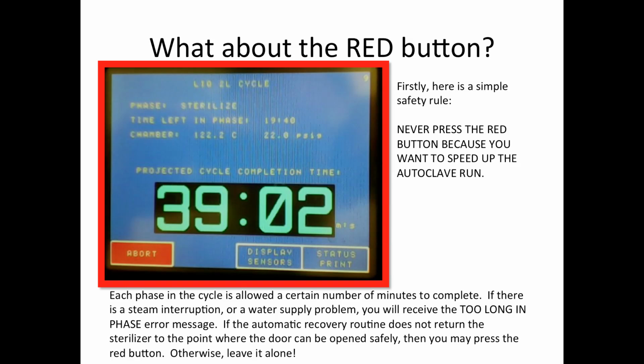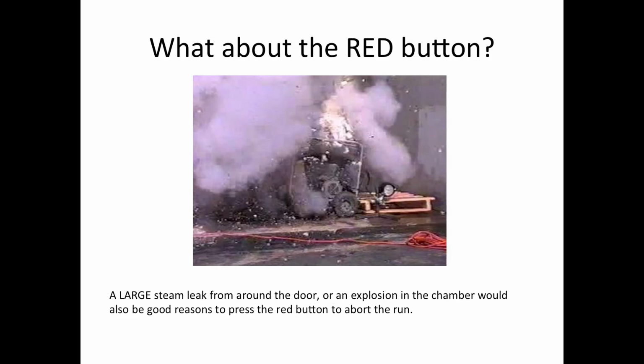Otherwise, leave it alone. If the sterilizer stops counting down, if there's no change to what is happening in the chamber, sometimes the software gets confused, you may need to press the red button and abort the cycle, particularly when you see that too long in phase error message. There are some other good reasons to press the red button, such as a large steam leak from around the door, or you hear your samples exploding in the chamber.